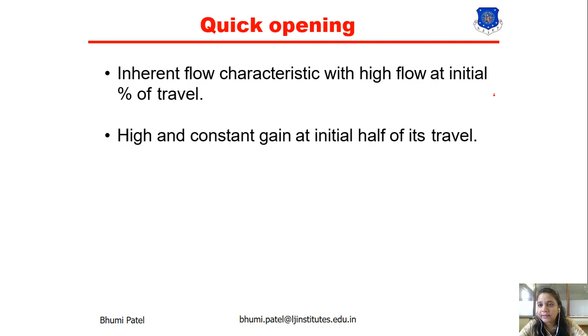So high and constant gain at initial half of its travel. You can see in this graph, this is the percentage valve travel and this is the percentage of CV. So at the initial valve opening we can get the maximum output. So decreasing gain at the travel above 70%. That means after 70% there will be a decrease, and we will get a steady output up to 100%. So in the quick opening we can get the maximum output at the initial flow rate.